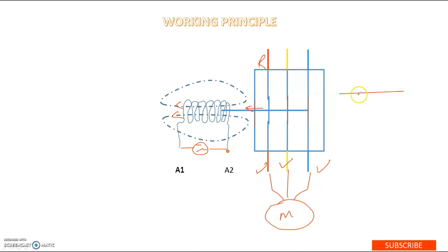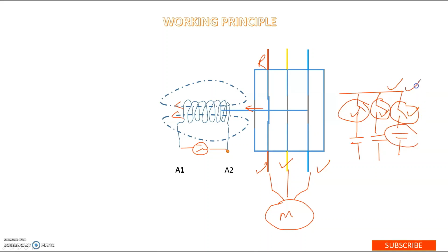in my case, if you have watched a previous video, we have talked about reactive power compensation, about power factor management using the capacitor bank, in which there's a continuous requirement of switching the capacitors on and off. These switches, which are being used to switch the capacitor to the bus or off the bus, are basically contactors which are controlled by the reactive power controller.